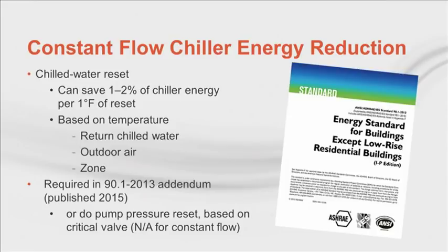This model energy efficiency standard has been inconsistent on chilled water reset. It was in, then it was out, and now it's back in the newly released 90.1 2013 mid-cycle supplement. The new version gives two alternatives, either pump pressure or chilled water reset, based on critical valve position. We'll compare these two options for variable flow systems. But for constant flow systems, chilled water reset is the most common control optimization because the pump energy is constant. We don't have additional pump energy to offset our chiller savings. This is not the case in variable flow systems, and we'll come back to this later.